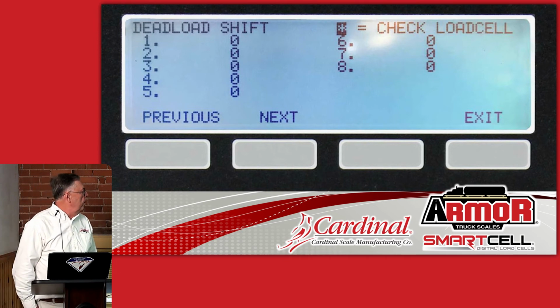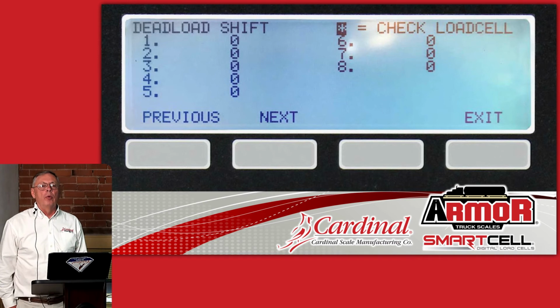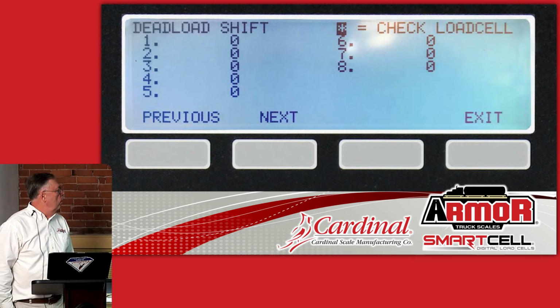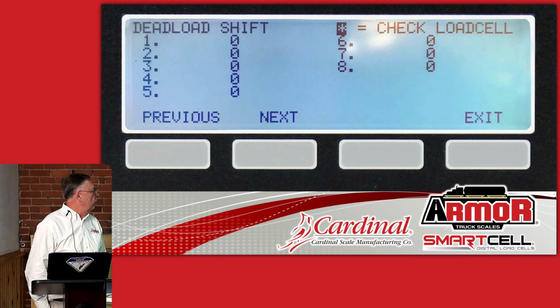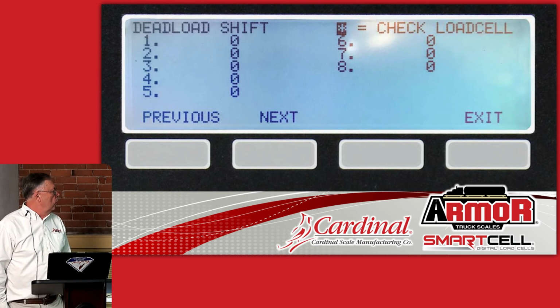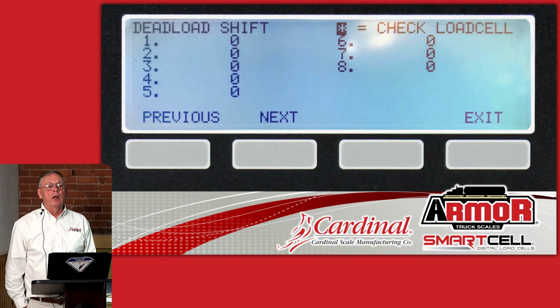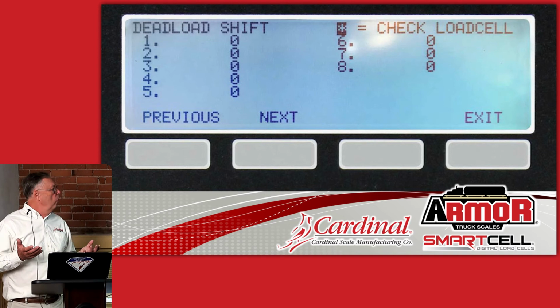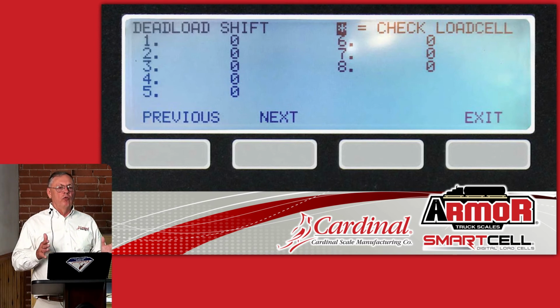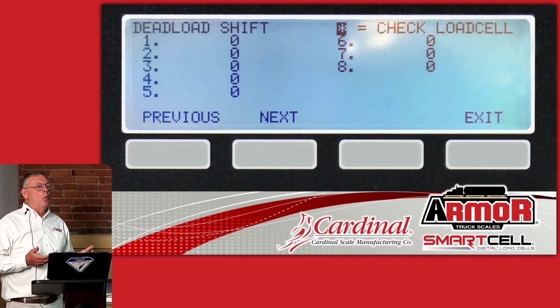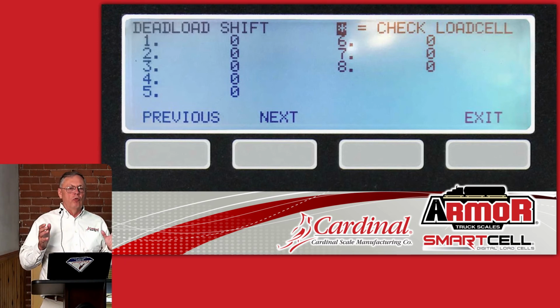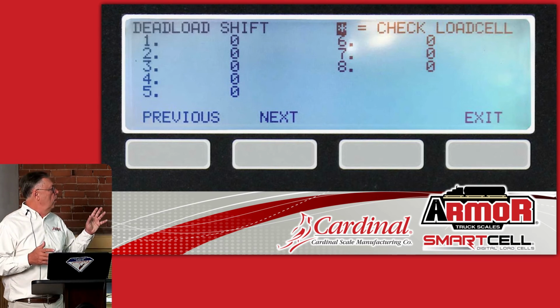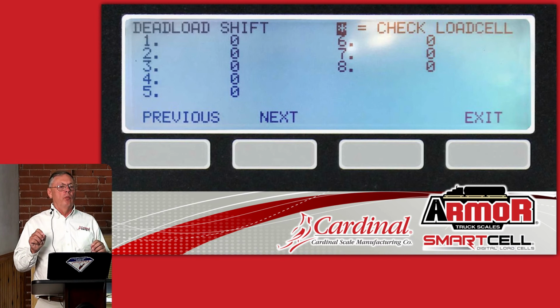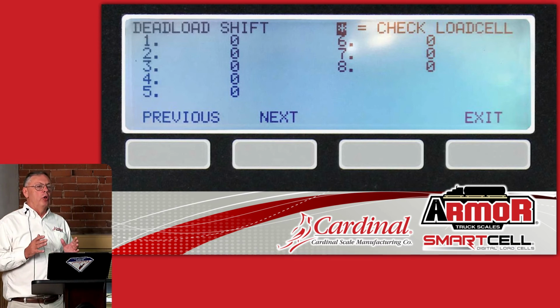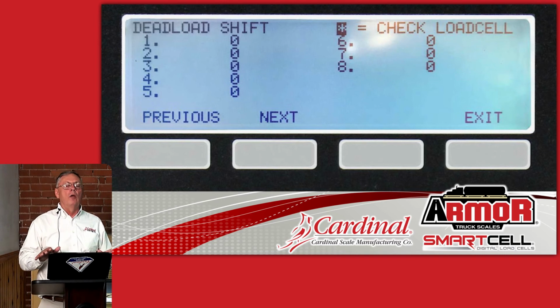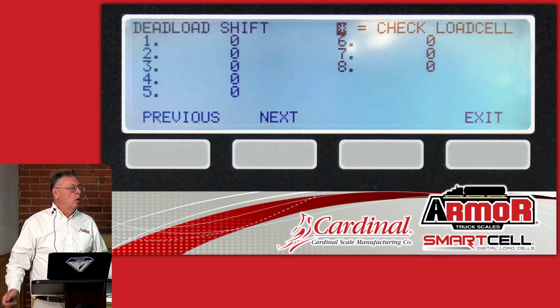This next screen is going to alert you to the problem with the output shift of a load cell. And normally if there's a problem with the dead load shift, there'll be an asterisk come up beside that load cell, and there'll actually be a number there, where these are all 0 because that scale had just been calibrated. Over years, you're going to see maybe a little bit of weight there as the 0 balance of the load cells change a little bit. You'll also see weight there if there's debris on the scale. If a truck's sitting on the scale, you're going to see a bunch of load cells with asterisks beside them. The diagnostics information should only be used when the scale doesn't have any weight on it, so that we know those are readings from the 0 of the load cell that we're getting.